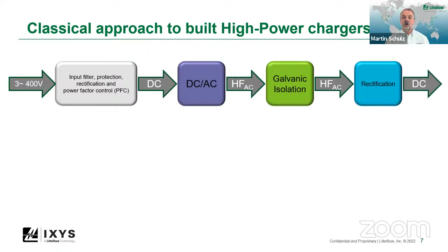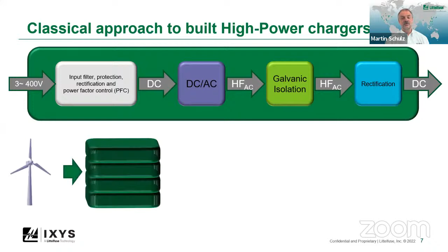All of this is packed into one subsystem or charger module. And then the energy coming from the grid is handled by a multitude of those modules. So they get stacked to increase the output power to provide power to high power batteries. Single units today are constructed to support something like 60, potentially 100 kilowatts from a three-phase input, which already is a lot. And stacking is done to upgrade the power level on the one hand, potentially, depending on the control structure, also to achieve redundancy.